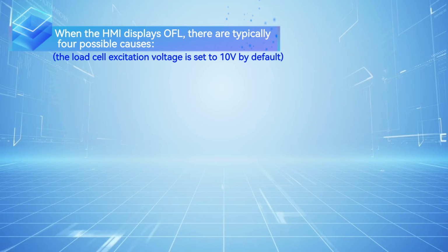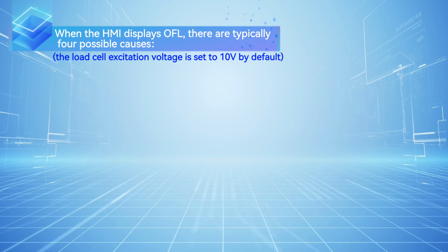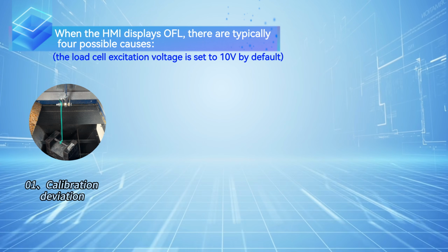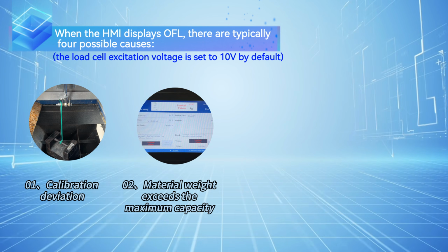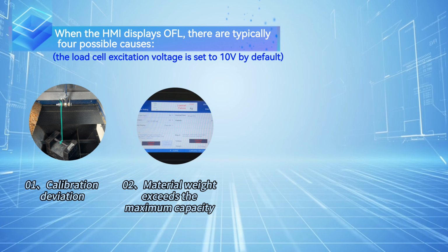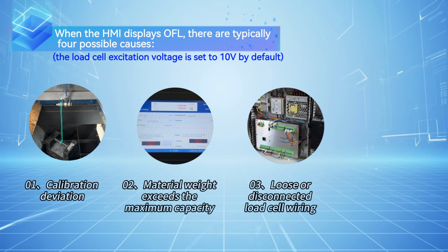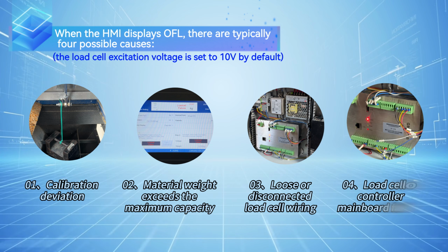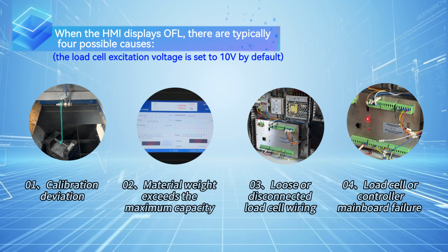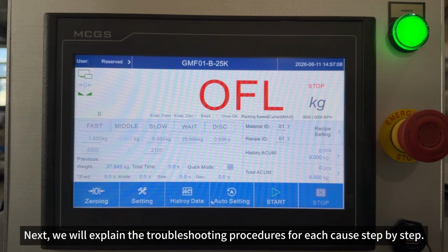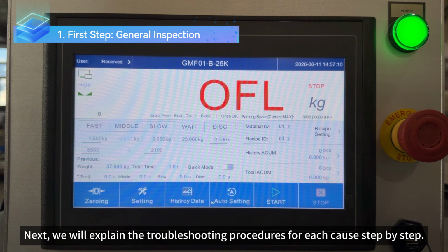When the HMI displays OFL, there are typically 4 possible causes. 1. Calibration deviation. 2. Material weight exceeds the maximum capacity. 3. Loose or disconnected load cell wiring. 4. Load cell or controller mainboard failure. Next, we will explain the troubleshooting procedures for each cause step by step.